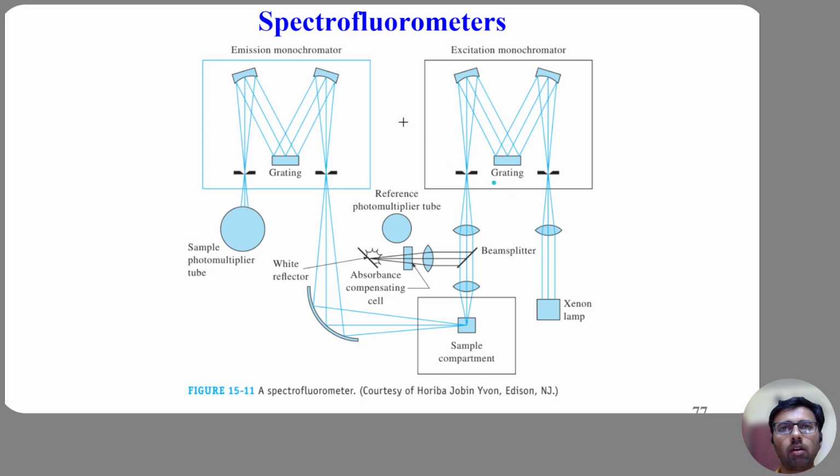Next is the architecture of the spectrofluorometer, to which we will now upgrade. The most obvious difference: no simple optical filters. Instead, the instrument uses two motorized grating monochromators, the first for excitation and the second for emission. The radiation source is typically a high pressure xenon arc lamp. This lamp produces an intense continuous spectrum.